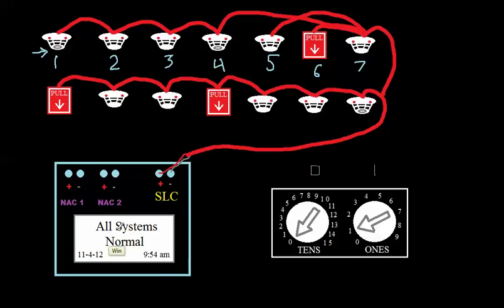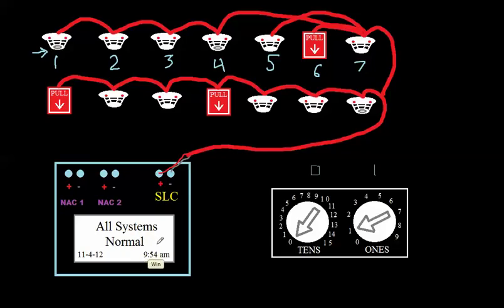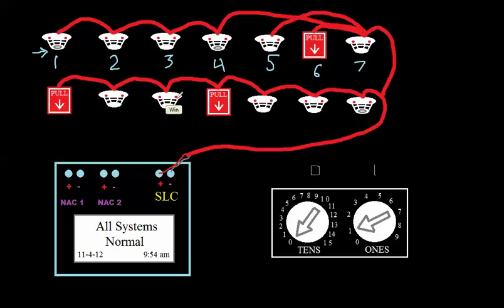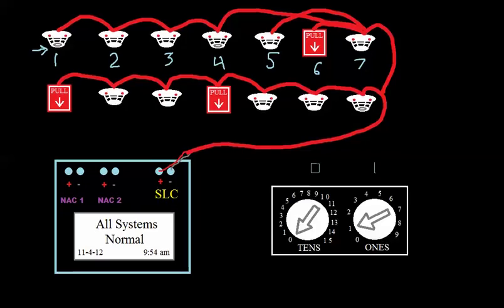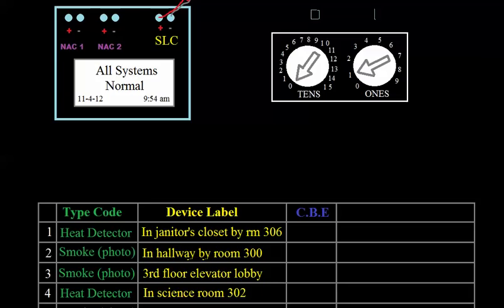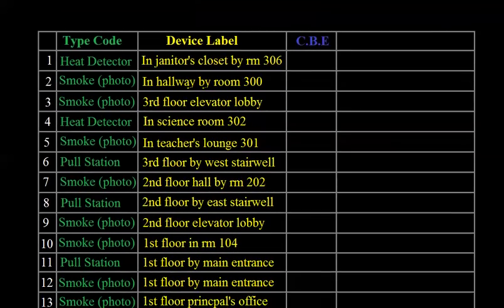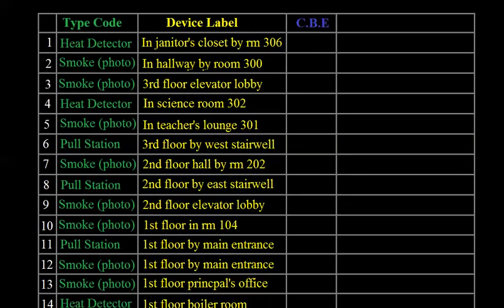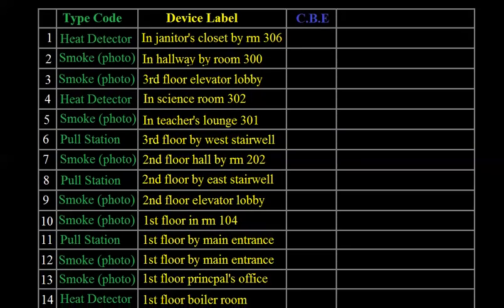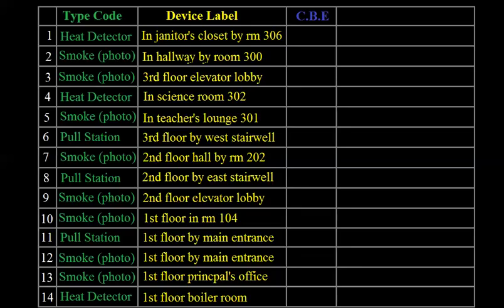You can go back through and look up, well, what happened? Maybe you're going on a service call and the panel's going into trouble intermittently. In the old days, you wouldn't be able to really tell what was going into trouble. Whereas now these panels will keep a history and you could say, okay, well, device three was intermittently going into trouble. But let's look at what we would have to tell the panel. I made this little chart that would be similar to what you would see if you were using some software to program this panel. This is my example of kind of like a software interface that you would hook your computer up to the panel, or you could go and just do it through the panel's onboard menu. There's a couple of important things that we have to tell the panel.